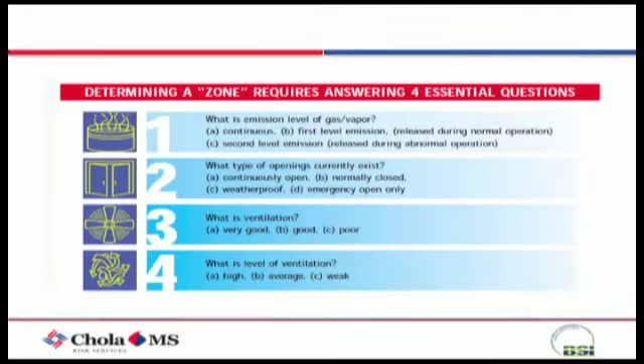First and foremost, you will not be allowed to keep a petrol bunk in a closed room. Assume sometimes it's not rich in mixture. Rich in mixture would be, say, at the 100th two-wheeler you are going to fill. At some point it would have crossed from the LEL level. Say at the 30th bike I am going to fill, the vapors could be different; at 40 two-wheelers different; at 50, different. Only at 100, when the volume inside the room totally becomes rich in mixture, might it not catch fire. But before that itself, it would have started somewhere or the other, it could have caught fire when there were only some 20-30 bikes getting filled.